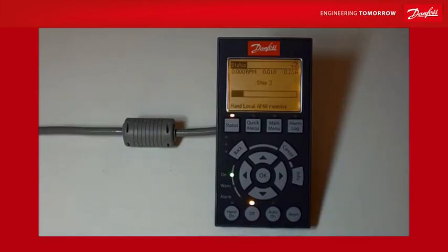Now we're in step 2, step 3. There are 16 steps in all. Let me just tell you a little bit about what's happening while this is going on. First of all, obviously when you take the drive out of the box and you put the motor nameplate details into the drive, then it goes away and looks at a lookup chart really, to look at typical values for that motor that you've described in the setup. Now that's all very well and the drive will work fine, but if you do these tests, it means that the actual resistances and things are actually calculated, and you get much better performance.